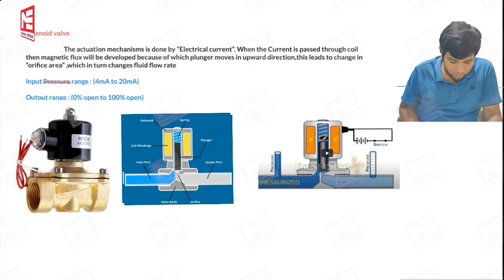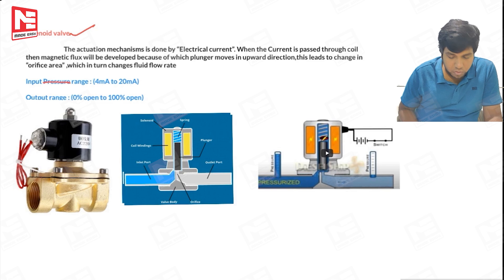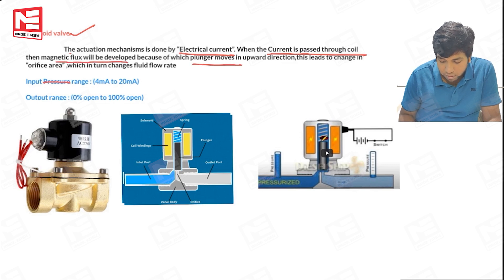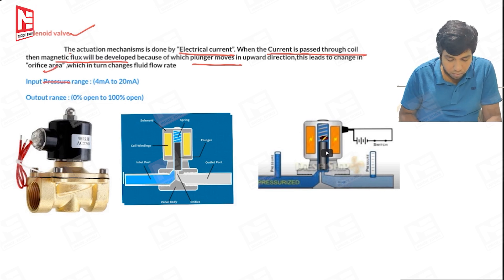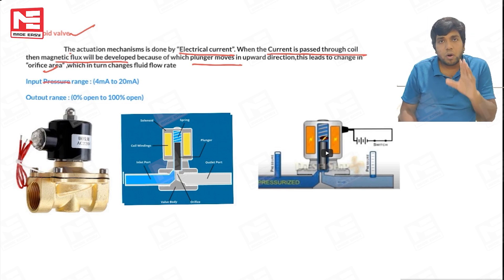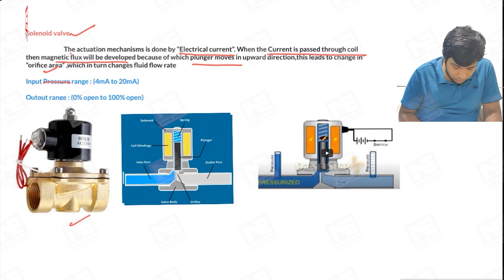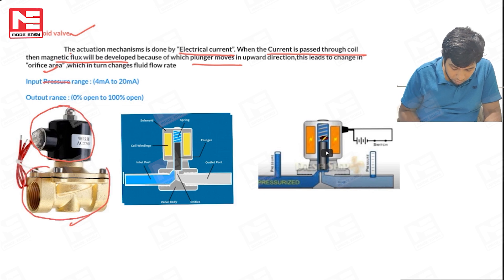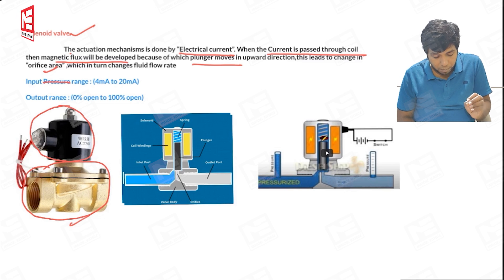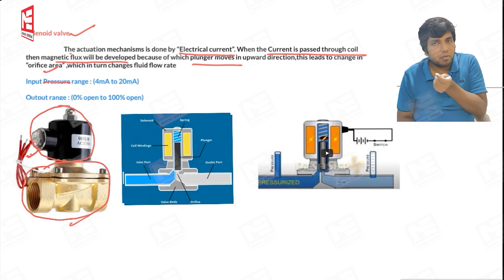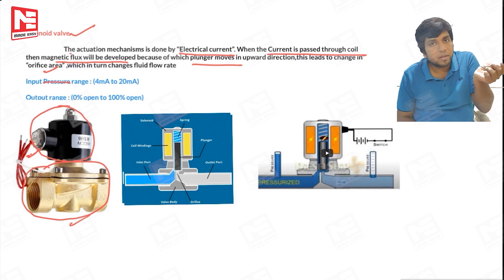The solenoid valve is an electrically actuated valve. The actuation mechanism is done by electrical current. When current is passed through the coil, magnetic flux is generated which moves the plunger upward — this changes the orifice area and in turn changes the flow rate. When you buy a solenoid valve it has an upper actuating body and a lower control valve body, with two electrical wires that can be plugged into a socket.